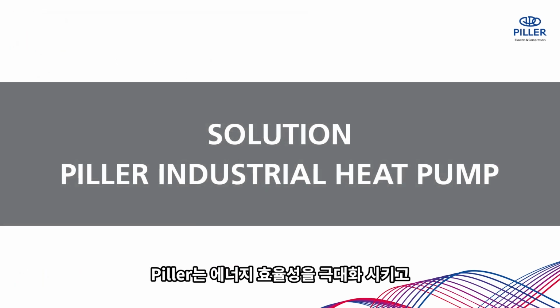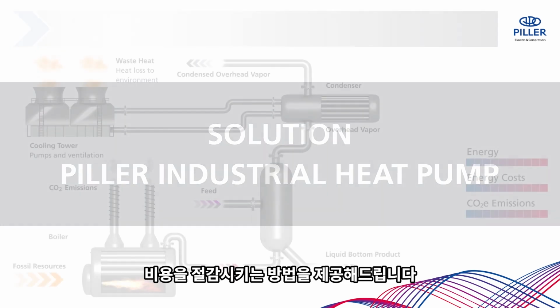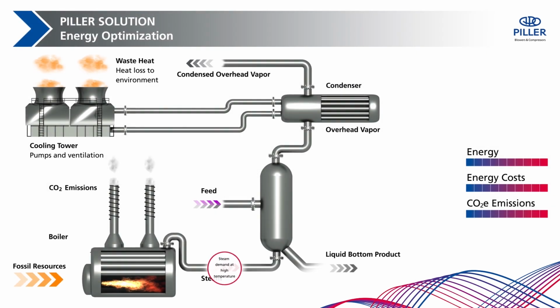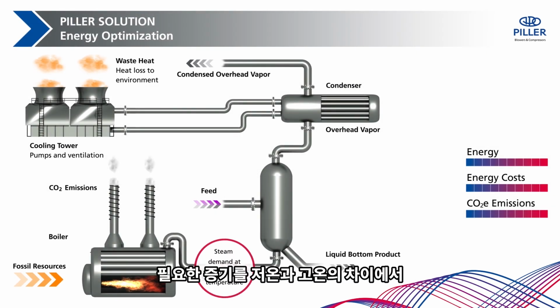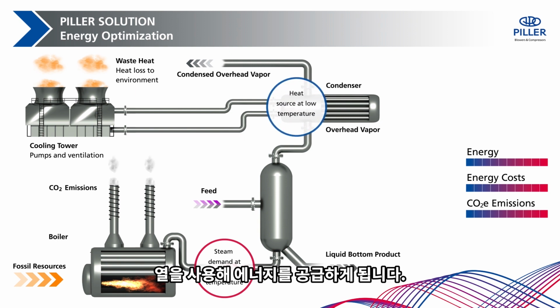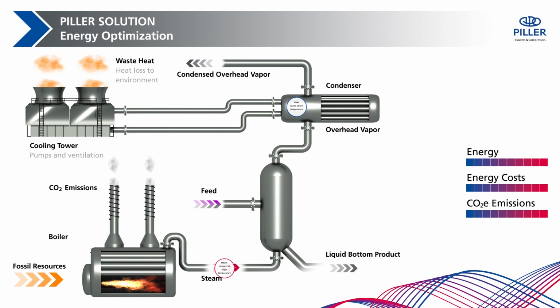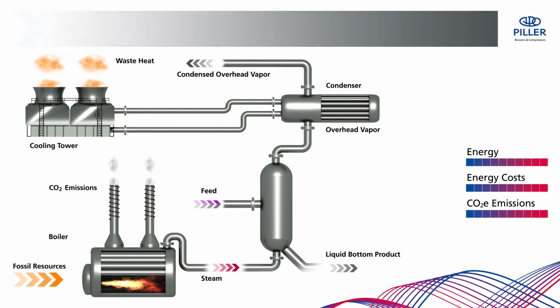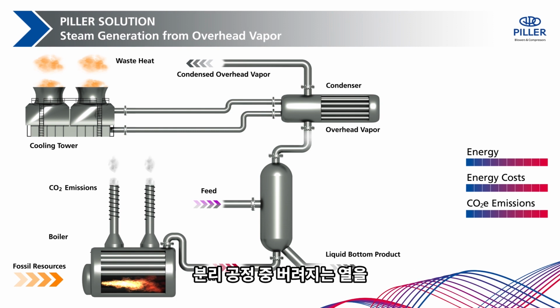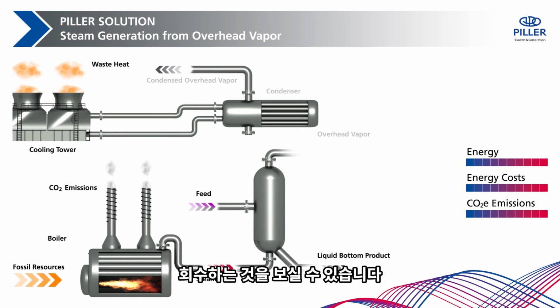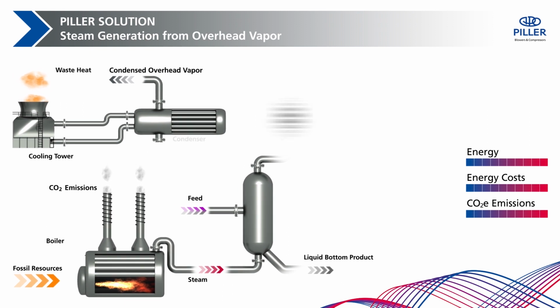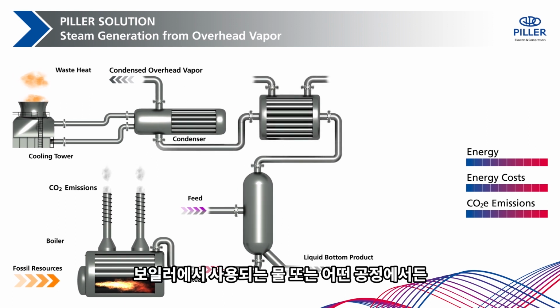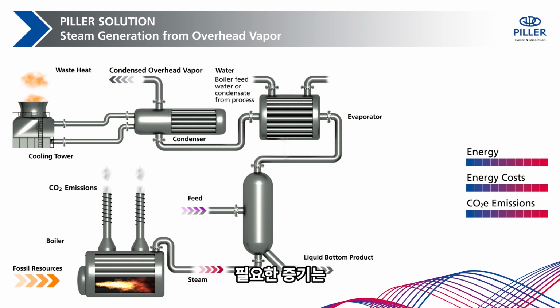PILLER offers the solution for more energy efficiency and cost reduction. The energy supply is optimized by linking the steam demand with available waste heat sources. Due to the temperature difference between low-temperature waste heat and high-temperature steam demand, a heat pump is required. In this example, the PILLER industrial heat pump recovers the waste heat from the separation process in an evaporator. Boiler feedwater or condensate from any process can be used here. The required steam is generated at a relatively low pressure and temperature level.